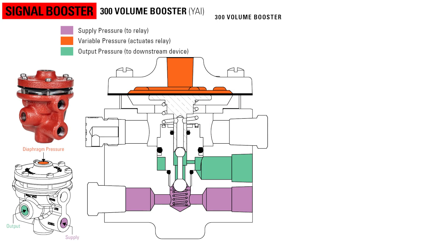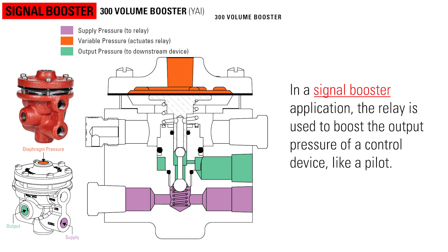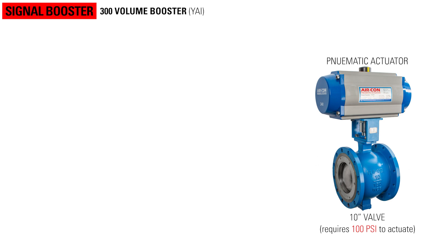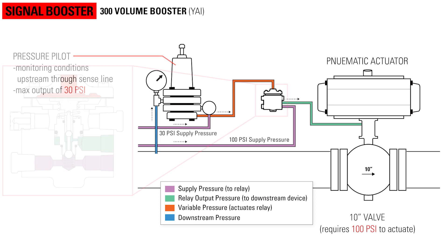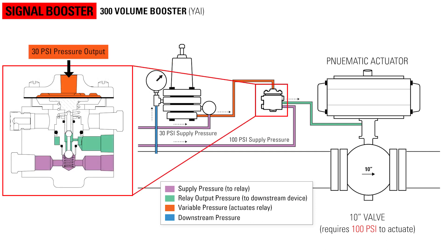In a signal booster application, the relay is used to boost the output pressure of a control device like a pilot. For example, here is a pneumatic actuator on a large valve that requires 100 psi to actuate. A pressure pilot is monitoring conditions upstream of the valve through a sense line. However, the pilot has a maximum output of 30 psi, well under the 100 psi required to actuate the large valve. So when the pilot reaches its set point, it sends its pressure output of 30 psi to the relay via the variable pressure line. The relay then responds by sending 100 psi from the separate supply line through its output to the large valve actuator so it can open.